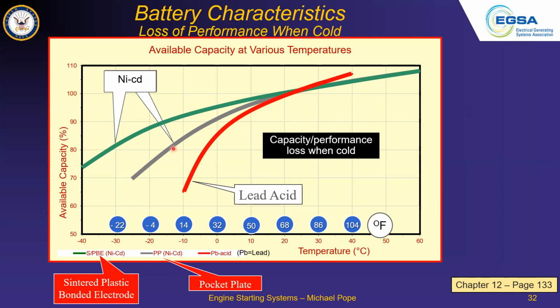There are two types of NiCad battery, and you can see that starting off at the same 100% capacity point, this one is not affected nearly as severely. Coming down to 14 degrees, this one still has a way to go before it drops only to 70% of its original capacity, and over here we've got 75% with a different technology. So where you've got really cold temperatures, the NiCad is the solution over lead acid.